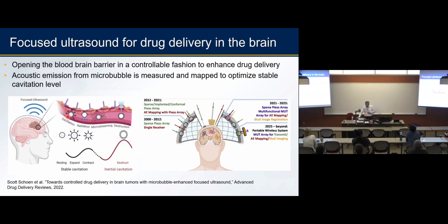So what you want to do is keep it in this region called stable cavitation. So there are two things. One is you want to locate it properly, and you're going through the skull, which is problematic, so we have to talk about that. But then, on top of that, you need to make sure that you're not doing too much, right? So what we do is we use the CMUTs as a broadband receiver, because when these microbubbles wiggle, they generate harmonics. So you can listen to those harmonics and tell how much they're oscillating, so that in a control loop, we can keep it at the right level.